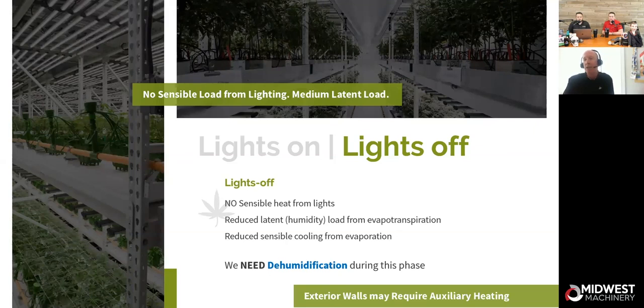Now, possibly it could need some heat, and that's where us understanding that heat loss equation comes in. So take a winter month and you've got external walls. Say you've got two external walls on this particular flower room over in the corner of your building, and it's 10 degrees outside. We could see the temperature in the flower room during lights off drop rather dramatically if you don't have good insulation on that. And that's why we ask, do we have any external heat gain or heat loss?